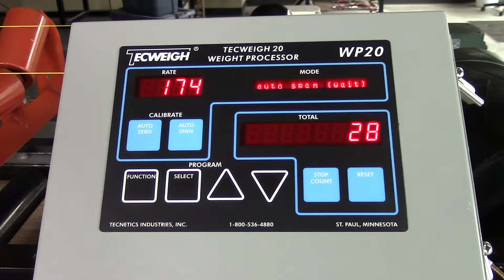So now you can see we have a simulated load value there from our test weights. And as soon as it does 2 complete belt revolutions, the span count will be complete. And there it says raise calibration weight. And as soon as we raise the calibration weight, the calibration is complete. That's a good number to write down, by the way, so that way you can always check it. Even if you don't have time to do a full span calibration, after zeroing it, which is much more important, you can always drop the weights on there to make sure it's showing what you expect it to.